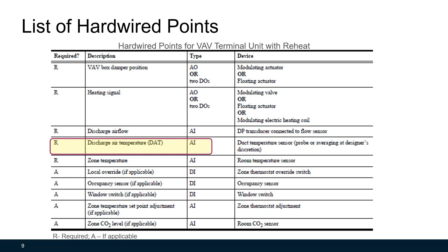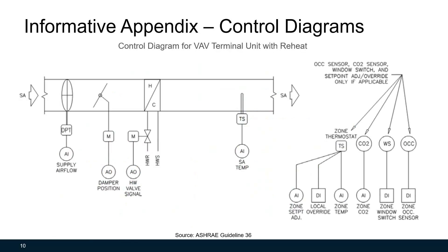Optional points include local override, occupancy sensor or window switch, and CO2 levels. Most of these points are for demand-controlled ventilation logic. Standard control schematic diagrams for these AHU and VAV terminal unit types are also provided in this guideline. The control and monitoring points shown in these diagrams can be found from the list of hardwired points. Note that in the diagram, discharge air temperature is labeled as 'SA temp' or supply air temperature.